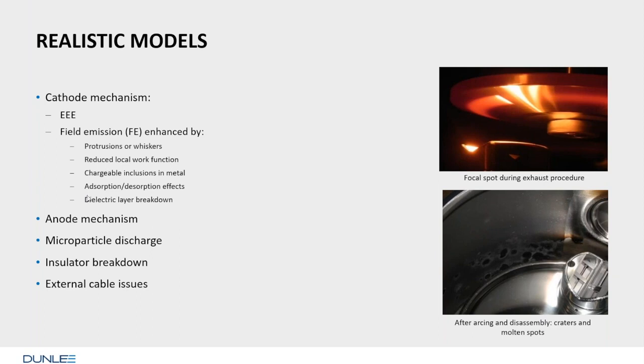There are also some alternatives which sometimes happen. This one is the anode mechanism. So this is cathode controlled. Another mechanism may be anode controlled. So for instance, here, returning to our picture to the right, you see here the very hot focal spot. It's about 2,500 degrees. If we go up further, 3,000, 3,200, up to the melting point of tungsten, then we see that plasma can also be generated here on that end if the anode is heated too much. And then a plasma cloud can develop from here.